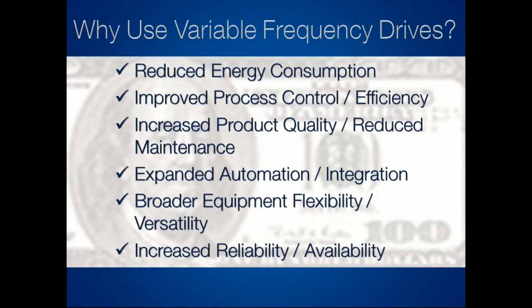Then, of course, we're going to have improved process control and efficiency. So when we can control the speed of our motor, we gain a lot of benefits and we have a lot more flexibility. When we have the exact output we need, we're able to be much more efficient. It can also help improve the actual quality of the equipment that you're working on, okay? So you're not having to go out and do a bunch of maintenance on a bunch of equipment. This VFD is actually helping your piece of equipment run better.